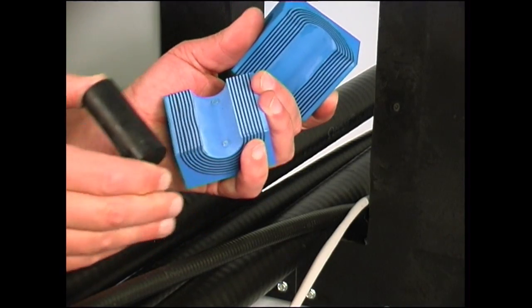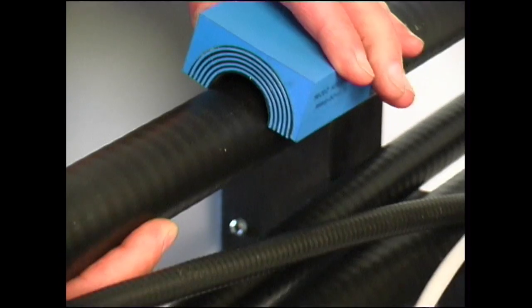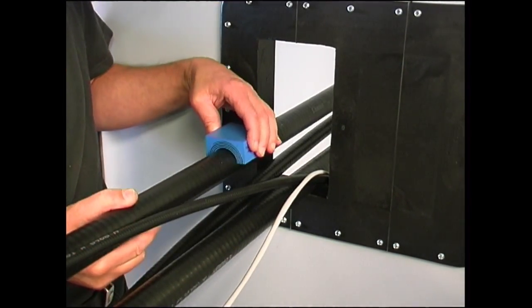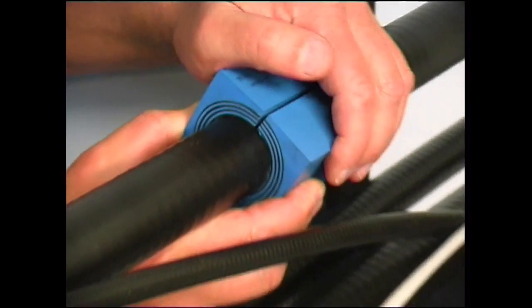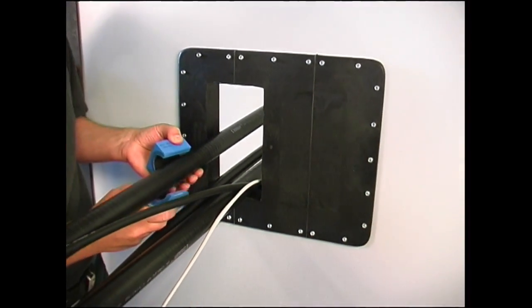Adapt the modules to the right cable diameter by removing layers from each half. Peel off each layer until the module fits perfectly. It is important that there is a 0.1 to 1 mm gap between the module halves when fitting the cable.